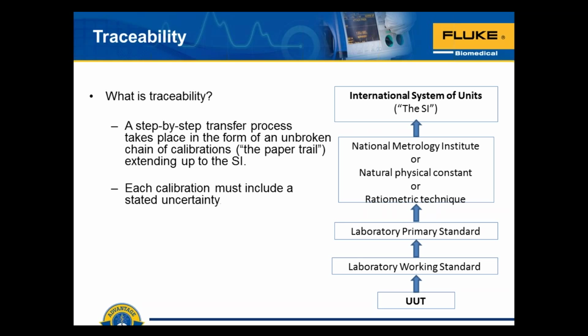Traceability is a step-by-step transfer process that takes place in the form of an unbroken chain of calibrations, that is, the paper trail, extending all the way to the SI, the System International, that is the unit of measure and its original source. Each calibration must include stated uncertainty, and so you should be looking for the disclosure of those uncertainties of the test instruments that are used to calibrate your test instrument, and you should be prepared in your biomedical department to provide your uncertainties, because they add to the stack up of uncertainties all along the pathway of traceability.